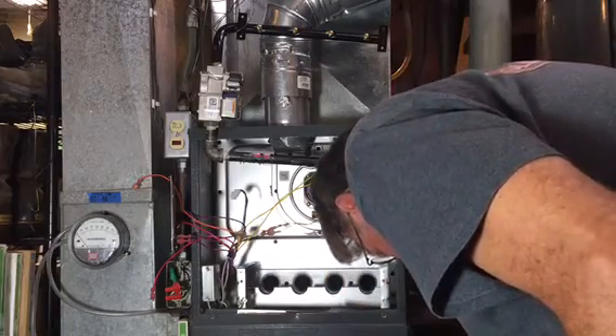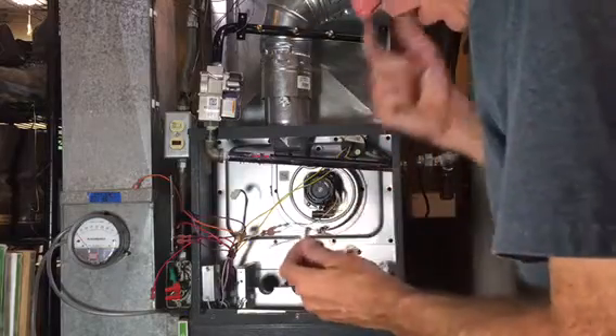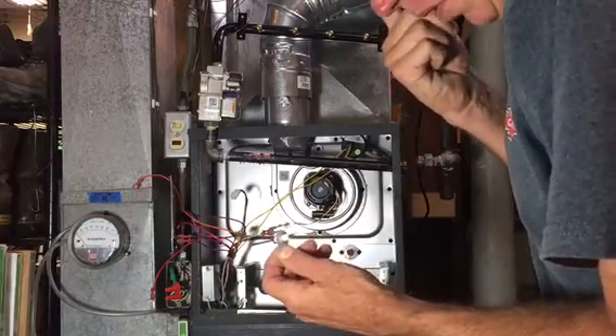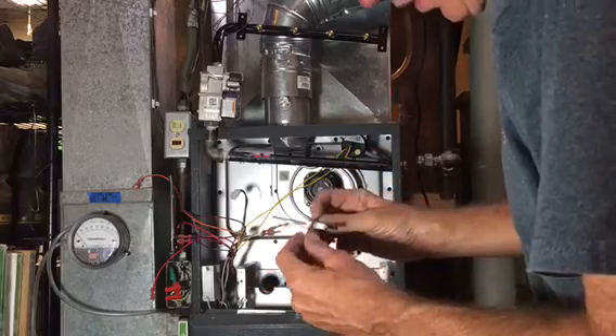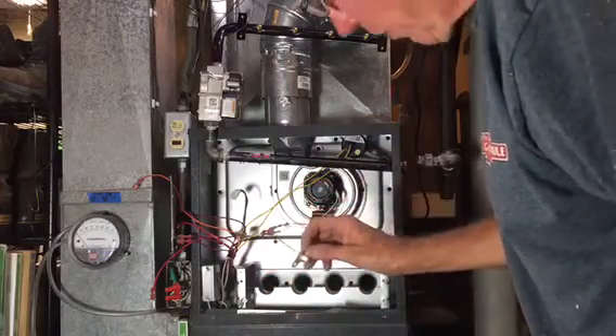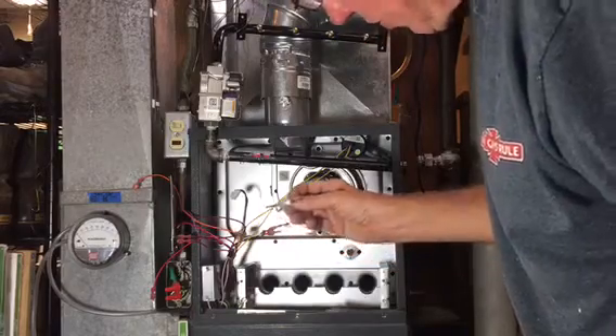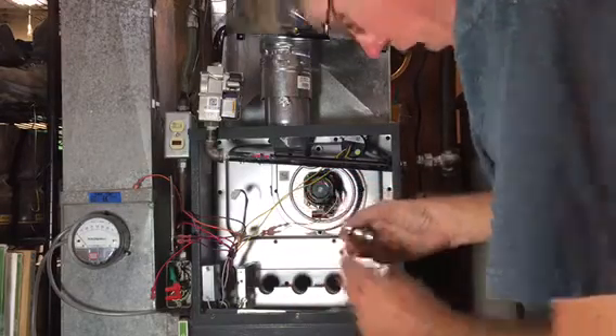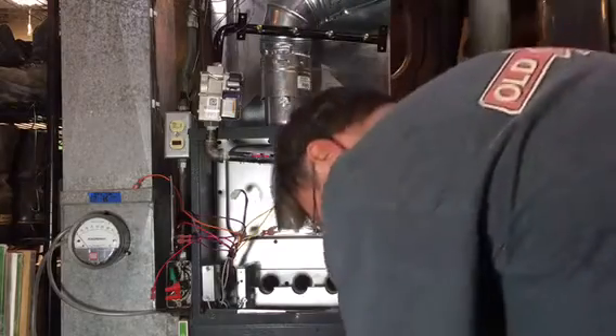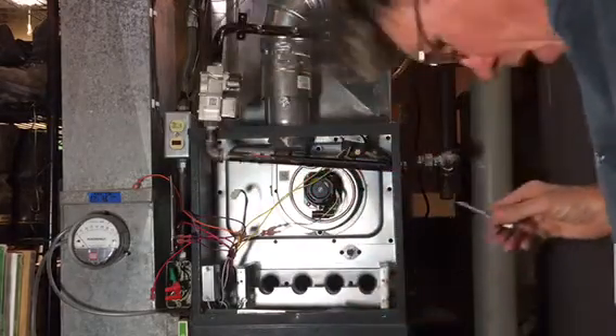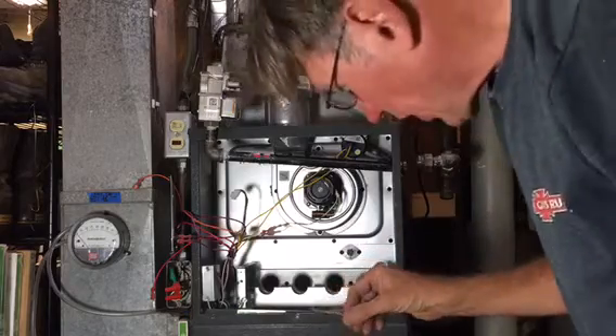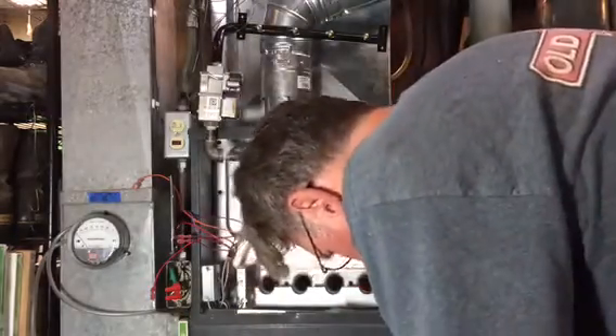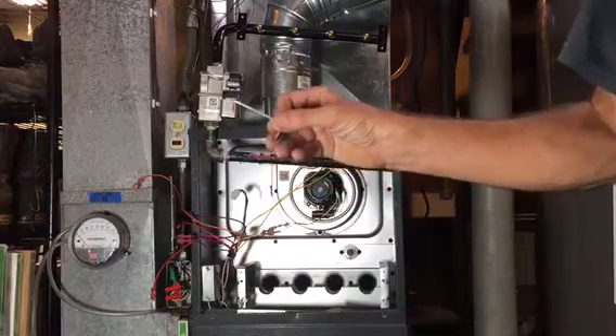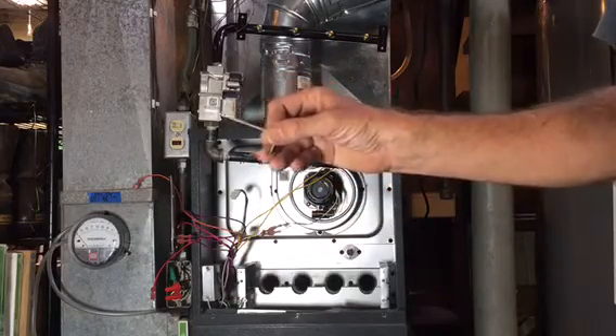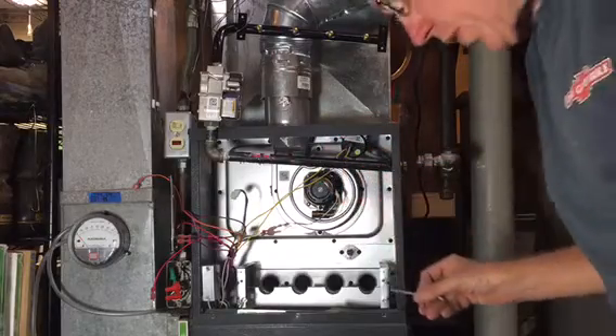Now the other thing is the sensor here. We have to measure that. It's supposed to draw a very small range of current, and that has to be when the unit is operational. And I've got the meter in series, so that measures microamps, so it takes a very small amount. One thing though is to clean that every service time, because it tends to get oxidized from the flame. Just very gently with some steel wool, which I thought I had here. I'm not finding it at the moment. Let me see if I can find that.